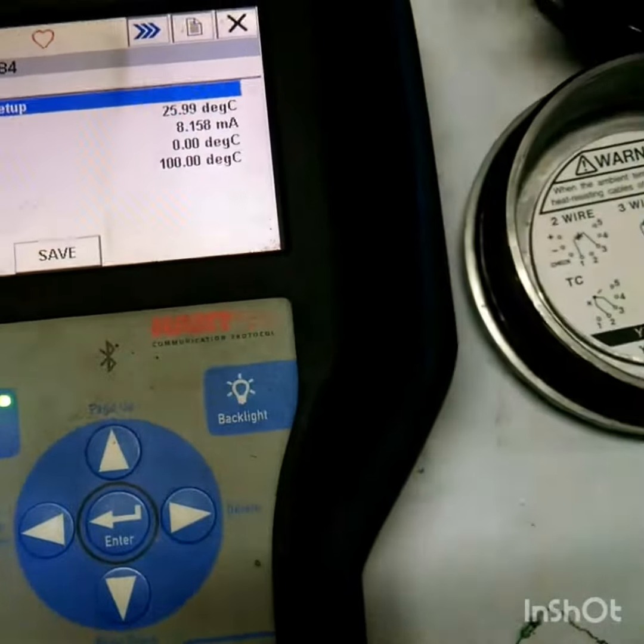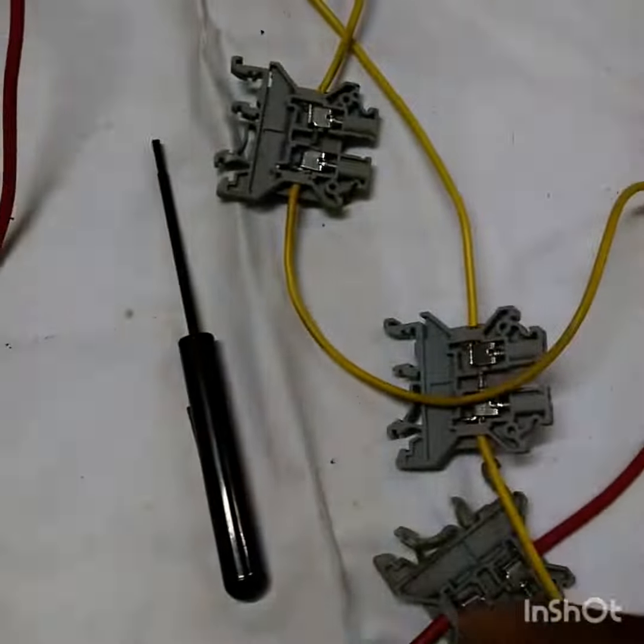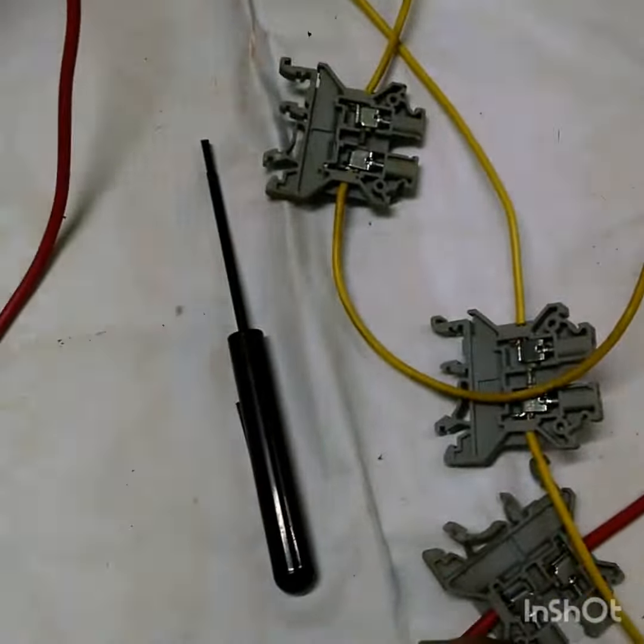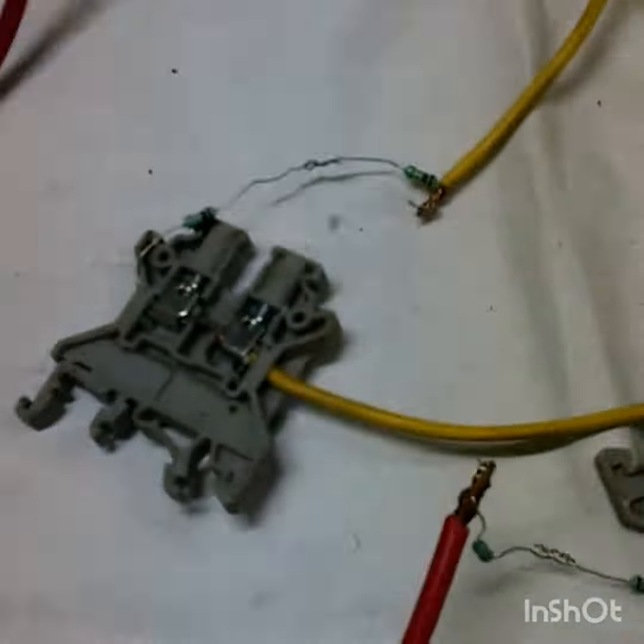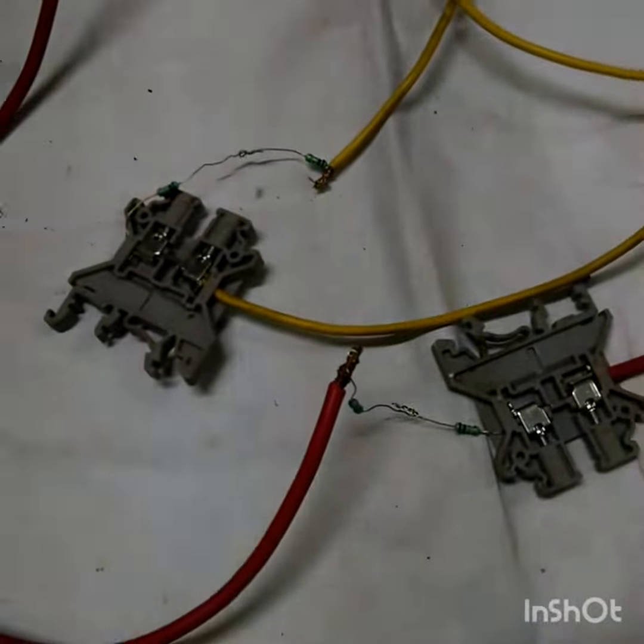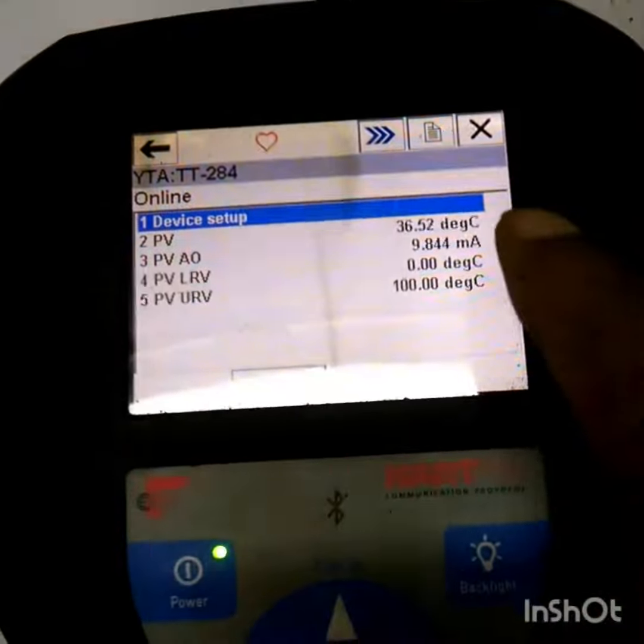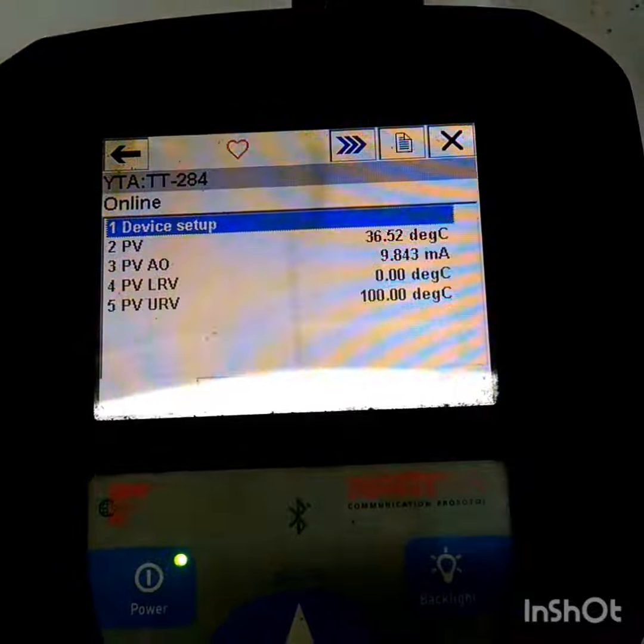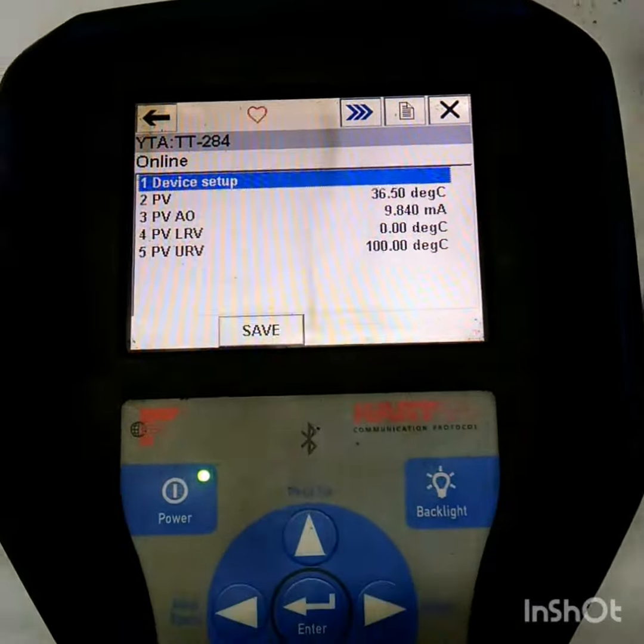Now I will put this resistor across this RTD cable and we will see how much the temperature changes. You can see I am getting 10 degrees more on the two-wire RTD.